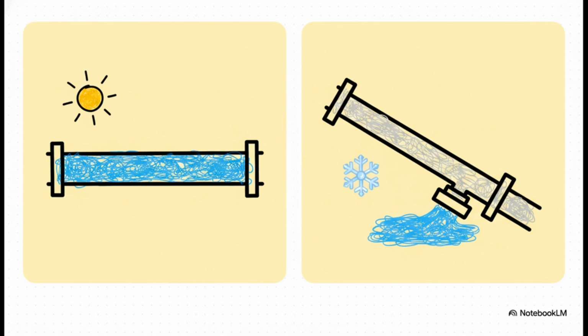A wet pipe system is the simplest, and it requires the least maintenance. It literally contains water under pressure at all times. This means the exact second that glass bulb shatters, water is instantly spraying. But here's the catch. It can only be used where temperatures stay above 40 degrees Fahrenheit. If you have a freezing warehouse in the middle of winter, a wet pipe would just freeze solid and burst. And that's exactly where the dry pipe system comes in.